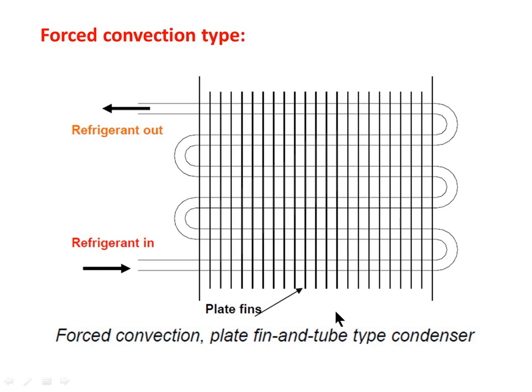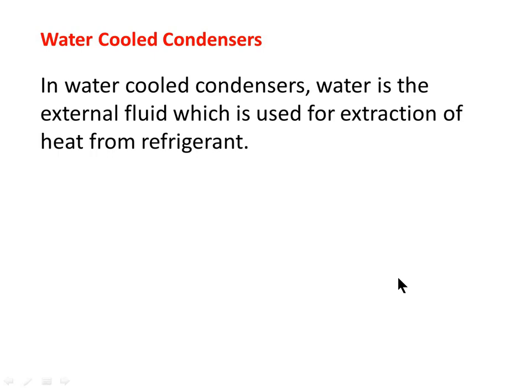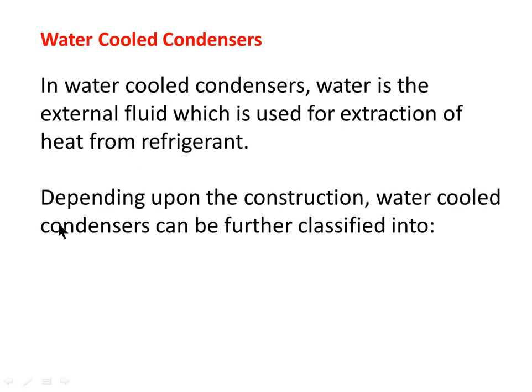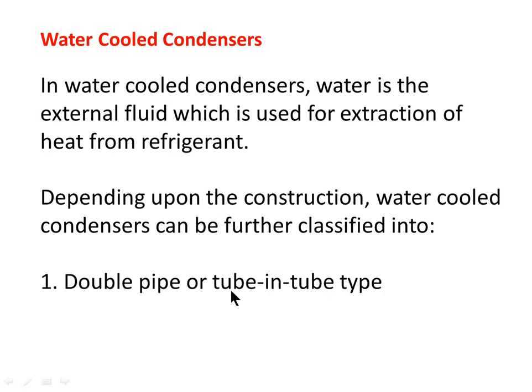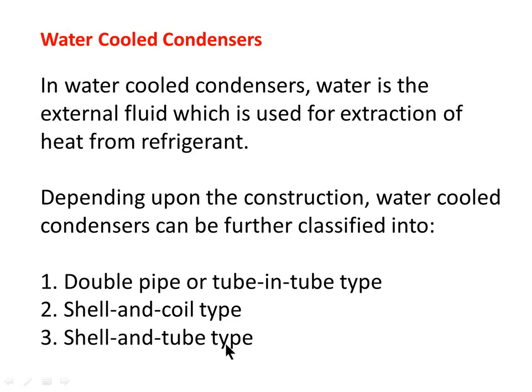Since no other medium of heat extraction is used, it is also an air-cooled type condenser. Next are water-cooled condensers. In water-cooled condensers, water is the extraction fluid used for heat extraction from the refrigerant. Depending on construction, water-cooled condensers are further classified into double pipe or tube-in-tube type, shell and coil type, and shell and tube type.